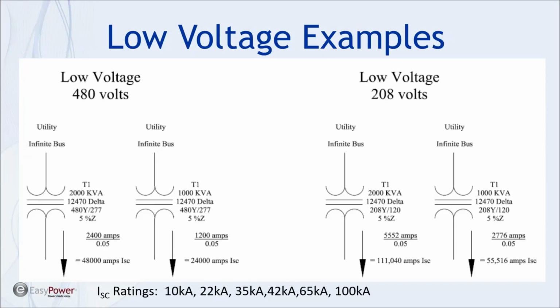And I also put down here the various ratings on equipment. When folks are putting in, I get a lot of calls to put in a 200 amp or a 400 amp panel board. These are the types of things that you want to know. I may want to discourage somebody from going to a local retailer and getting a cheap 200 amp panel board and installing it, for this very reason right here, as well as installing breakers in panel boards. You have to be careful of that as well. So these are the standard short circuit ratings that I'm familiar with. There may be a few more that I'm missing. I know that on fuses they go to 200 and 300 kA as well.